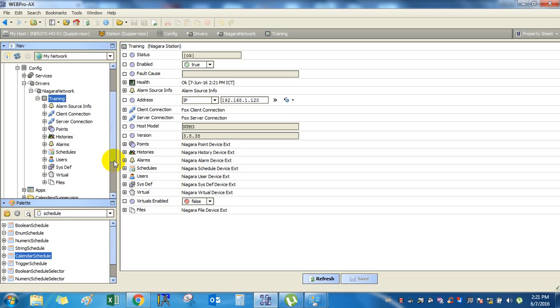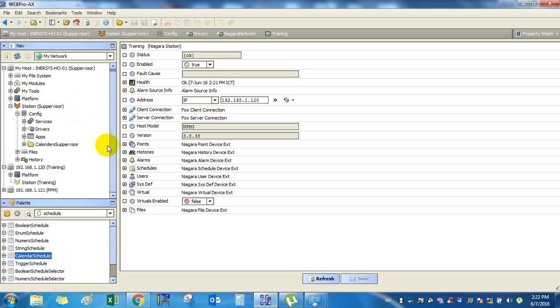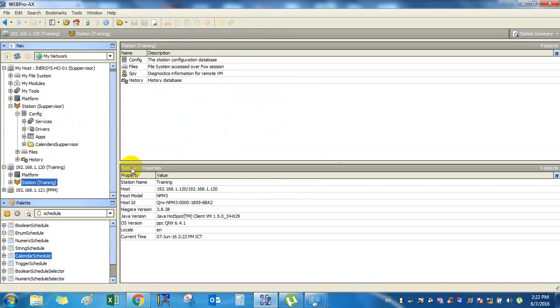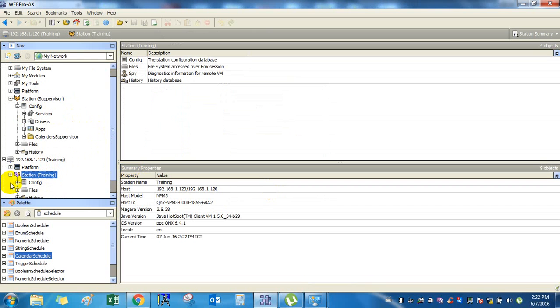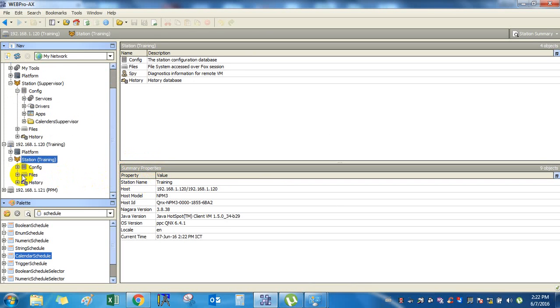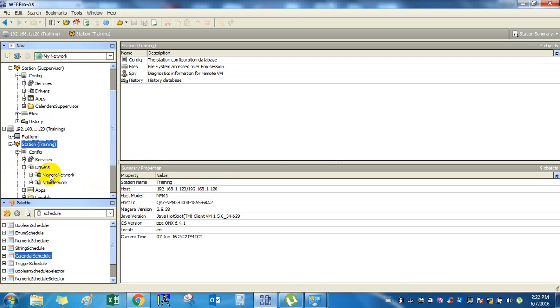Right? Now if I just want to check whether whatever I have done is correct or not, I'm going to go into supervisor. I'll go to the federal holidays and I'll add an event for today. I save it. Because my execution mode is manual, I will have to go to the schedule here in my station and execute so that the sync happens. And if I go to my loop lab now, my output has gone to 0 because supervisor told me that today is a holiday. Right?